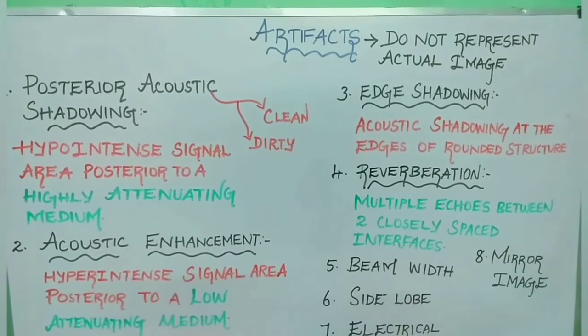Next are electrical artifacts. Electrical interference is basically caused by some problems in the machine output, or it could be related to voltage fluctuation, frequency fluctuation, or sometimes just electrical interference coming from adjacent electrical machines that are working at the same time as the ultrasound machine. Next is mirror image.